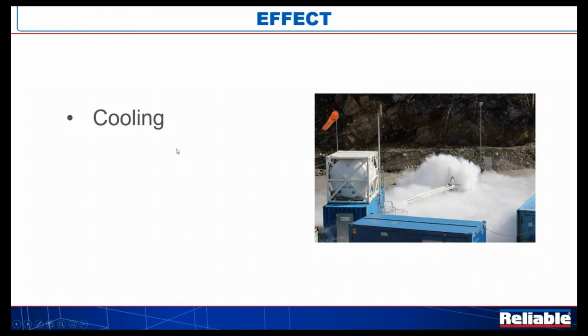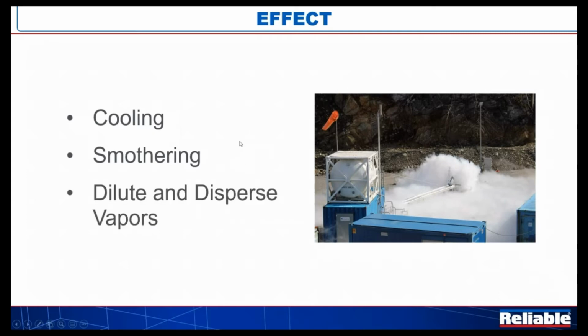When you break the water into smaller drops, there is much more surface area available to absorb heat. A pound of water, which is about 1/8 of a gallon, absorbs 1,150 BTUs as it converts to steam. So it's gathering that heat that's coming off, and it's simply cooling the environment down. When that water turns to steam, it starts wanting to drift downward, and it actually starts to smother the fire. So you see a slightly different fire protection process happening here, with cooling and smothering. And then finally, in the case of vapors, we want to take those water drops and start diluting and dispersing those vapors and get them out of the environment. So that's the effect of the medium velocity nozzles.